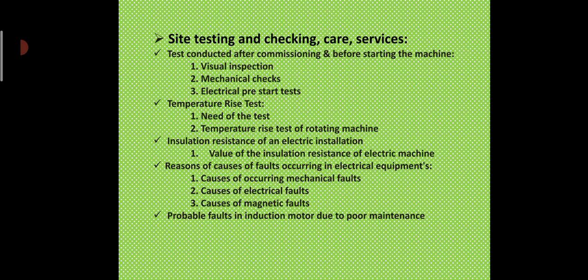Now, insulation resistance of an electrical installation. Insulation resistance of domestic wiring, factory wiring, powerhouses, substations, etc. is measured with the megger or insulation tester. This resistance is measured for two cases. First is insulation resistance between the phase and neutral wires. Second one is insulation resistance between phase and neutral wires with earth.